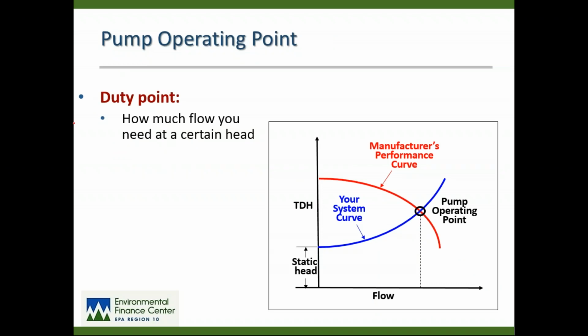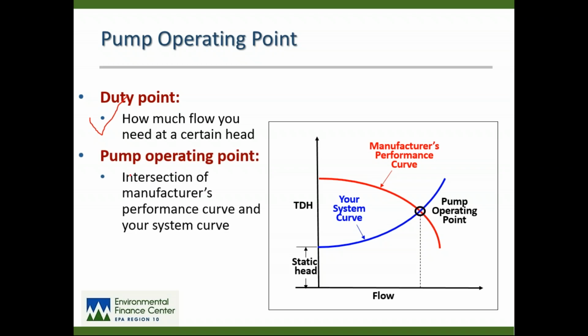Your duty point is how much flow you need at a given total dynamic head. Now, you know how much that flow is, or your engineer does, because he or she designed it to work within the parameters that you needed, your design data. Let's say you are pushing 500 gallons a minute to a tank up on a hillside that's 300 feet. So that is your duty point, how much flow you need at a certain head. The operating point is the intersection of your system curve, which is down here, and the manufacturer's performance curve, remember, which sloped downward. This operating point, that's where you want to be on the manufacturer's curve at the manufacturer's best efficiency point.